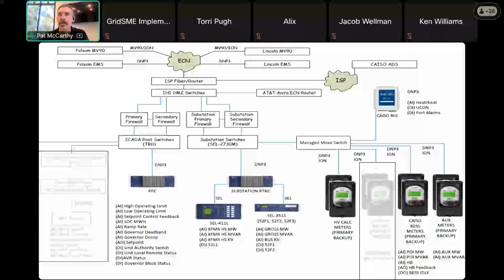You might find a little something—polarities backwards, or scaling off by a factor of 10. If it's small stuff and CAISO's got bandwidth, they might say, 'Looks like we have a little problem between that feeder relay and the substation RTAC, can you guys fix that in the next 10 minutes?' 'Yep, okay cool, let's start looking at the power plant controller while we get that fix in.' So CAISO is going to wander around the points list in this document to make sure they get all the testing done for each point within the allotted time.